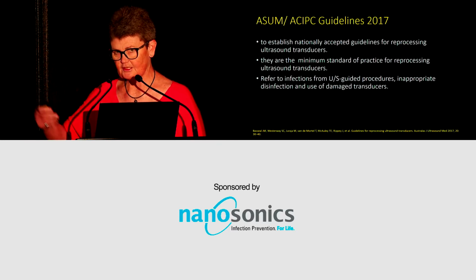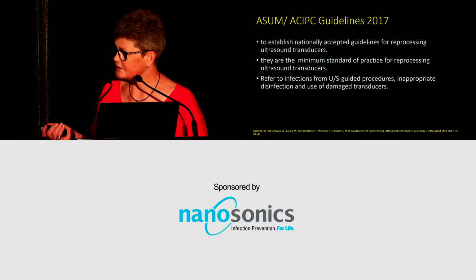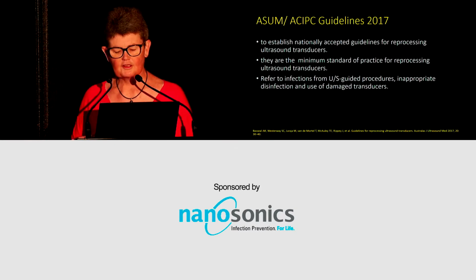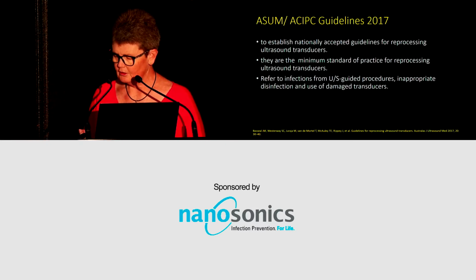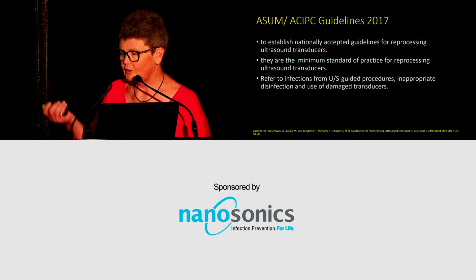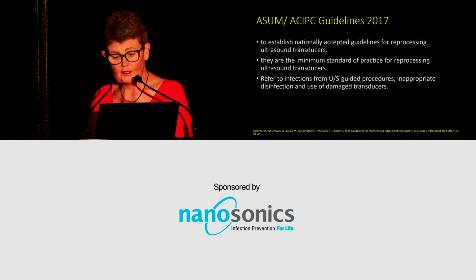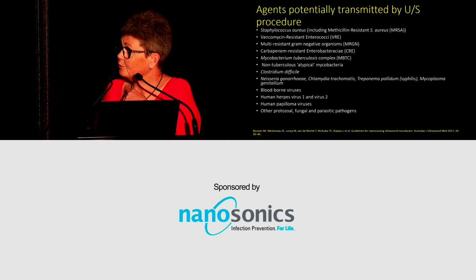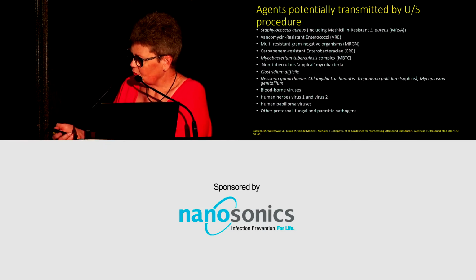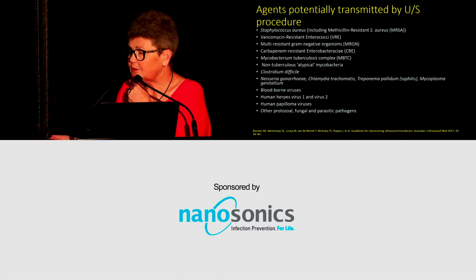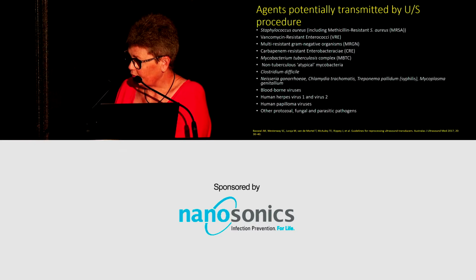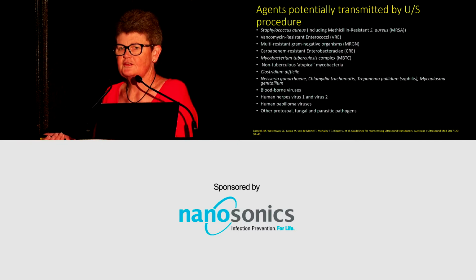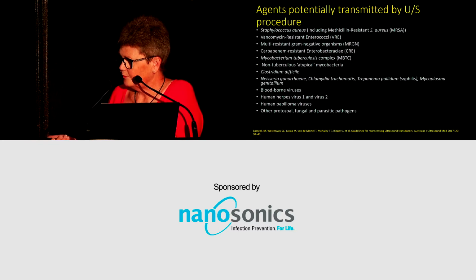It sets and gives life to the minimum standard of practice for reprocessing ultrasound probes, and it also makes good mention of other infections that have come from inadequate reprocessing of these ultrasound devices, where disinfection's been either inappropriate or where the devices have been damaged and therefore not reprocessed properly. All of this is concerning because look at the range of agents that are potentially transmitted. They're not just simple viruses, they're not just blood-borne viruses, they're bacteria, multiple resistant bacteria. So this is a very serious issue. Clostridium difficile, a huge problem for us from an infection control perspective, respiratory bugs, and then other protozoa, fungi, and parasitic pathogens.